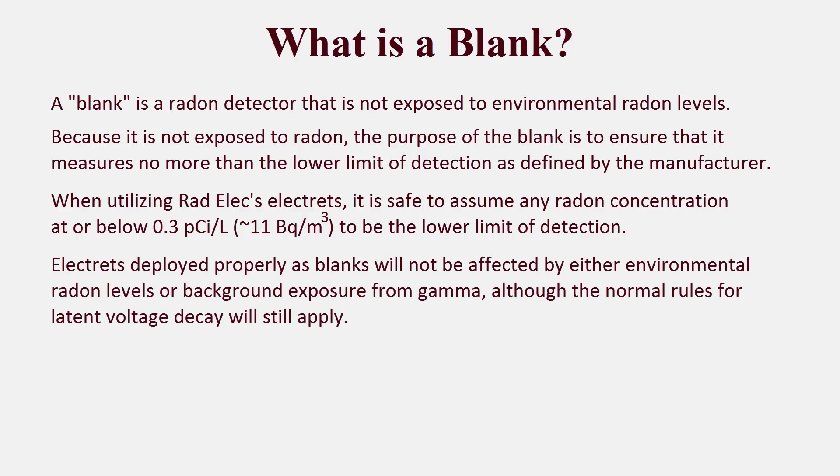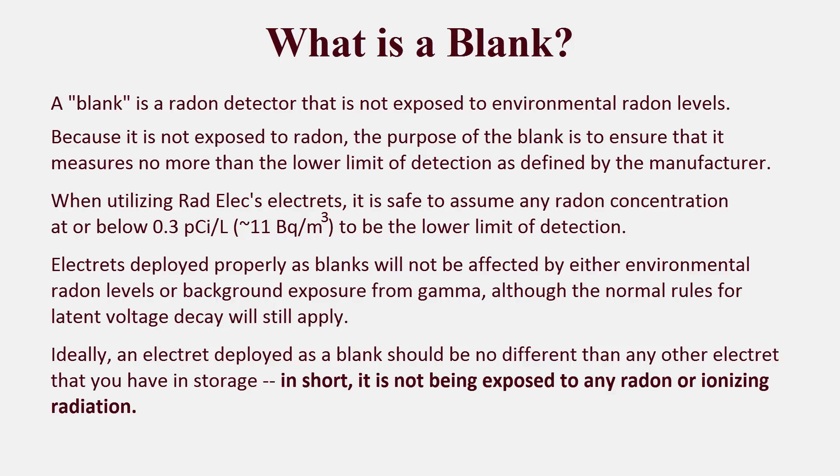Electrets deployed properly as blanks will not be affected by either environmental radon levels or background exposure from gamma, although the normal rules for latent voltage decay will still apply. Ideally, an electret deployed as a blank should be no different than any other electret that you have in storage — it is not being exposed to any radon or ionizing radiation. Because it's not being exposed to any radon, it shouldn't measure any. That's the goal of deploying a blank: to make sure that you're not accidentally measuring radon when you're not supposed to be.